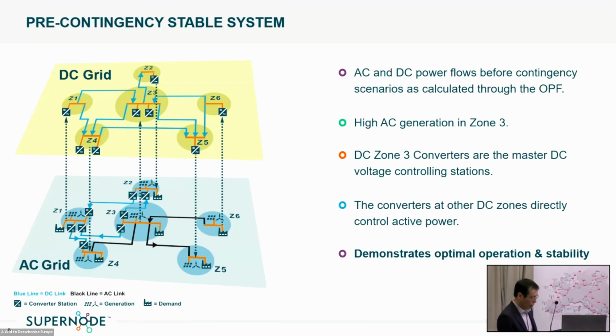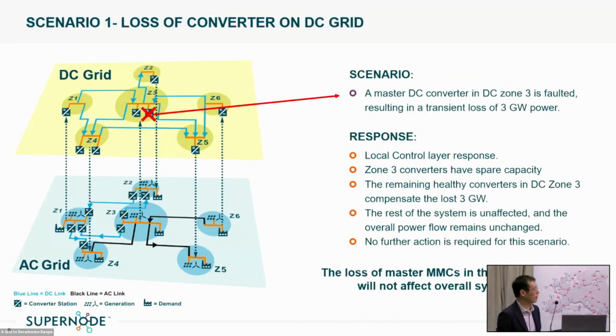For testing the behavior of the system, we use multiple converters in DC zone 3 to regulate the DC voltage in our DC overlay. They act as master DC voltage controllers to balance the overall power coming into and out of the DC grid. The main purpose is to demonstrate optimal operation and stability of the overall AC-DC hybrid circuit.